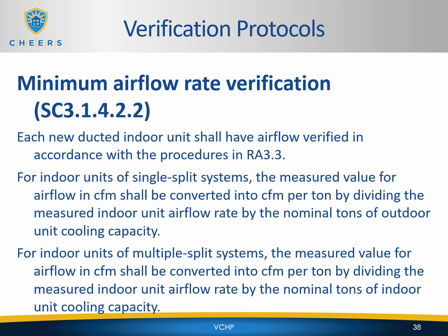Minimum airflow rate verification, and this is found in section SC3.1.4.2.2. So each new ducted indoor unit shall have airflow verified in accordance with the procedures in RA 3.3. So again, that's just your standard airflow verification that you do.